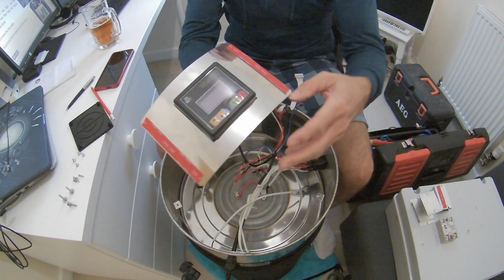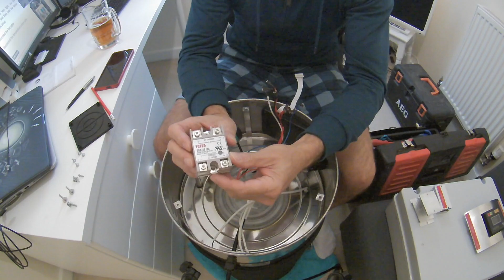So I've got the SmartPID itself, I've got an SSR, which is a solid state relay. Basically what it means is, on this side here you have a 12 volt feed, which will come from the SmartPID, and on this side here it's 240 volt, or whichever your denomination is, 24 to 380, but mine will be 240. This will be inside the circuit for the heaters, which are resistors effectively. And to turn this on and off, the SmartPID will send a signal on the low voltage side, which will flick a switch in here, to connect this, which will then complete the circuit and allow it to heat up.